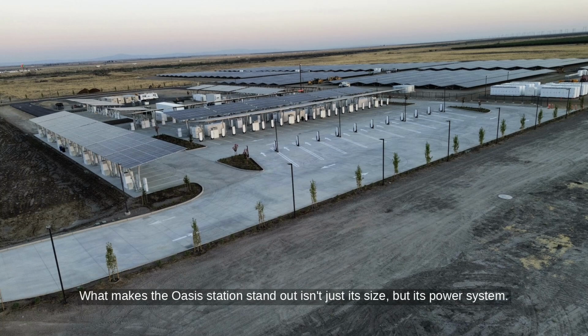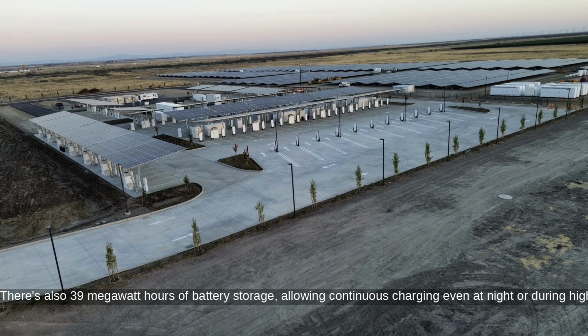What makes the Oasis station stand out isn't just its size, but its power system. It's powered mostly off-grid, using 11 megawatts of solar panels alongside 10 Tesla Megapacks, which together deliver up to 15.8 megawatts of peak energy. There's also 39 megawatt-hours of battery storage, allowing continuous charging even at night or during high demand.